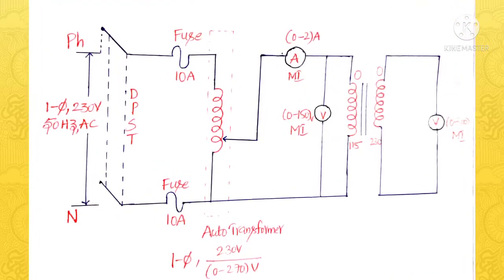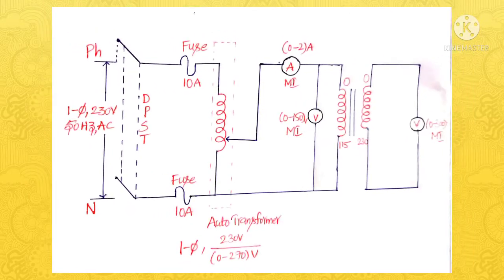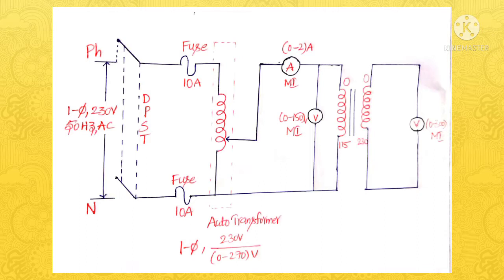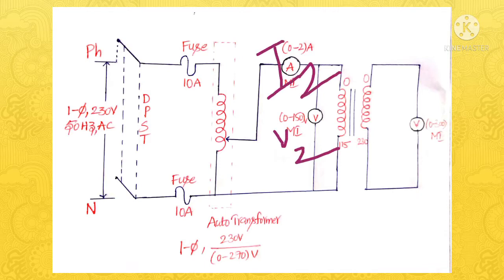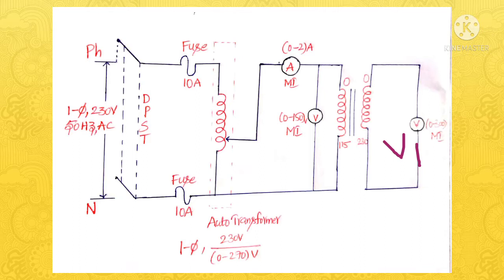In the second step, we will connect the circuit differently — there is an interchange in the connections. Previously, we gave the connections at the 230V side; now we are giving the connections at the 115V side. Keeping the autotransformer in the minimum position, we will close the DPST switch and then vary the autotransformer in order to measure different voltages and currents. As the 115V side is now considered as the secondary, the voltage across the 115V side is V2 and the current flowing through that side is I2, while the voltmeter connected across the 230V side measures V1.